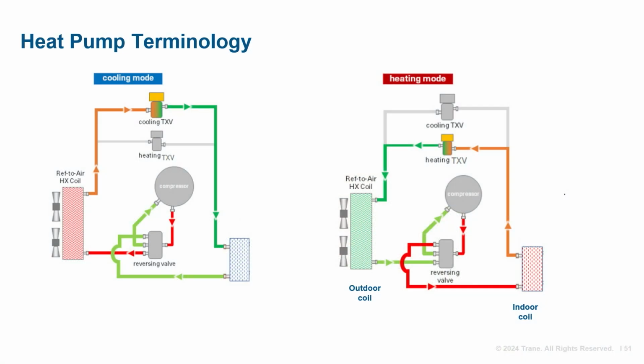Now let's take a moment to review the differences between heat pumps and the traditional cooling system coils. You might ask yourself, what's the difference? When we describe a heat pump, we must be sure to use the proper coil terminology. A typical cooling unit uses an evaporator and condensing coil. During the cooling mode, heat energy is absorbed through the indoor evaporator and is then rejected through the outdoor condensing coil. A heat pump uses the same refrigeration cycle but changes the refrigerant's flow and each coil's role. The heat pump cycle absorbs heat from the outdoor coil and transfers this heat to the space.